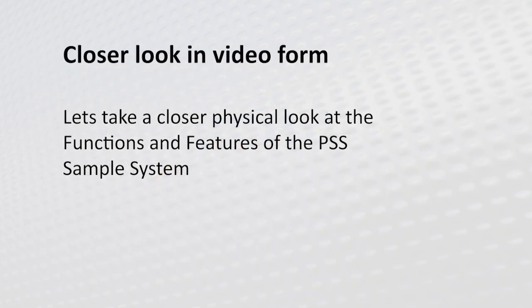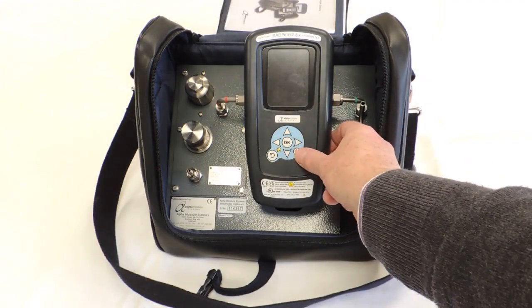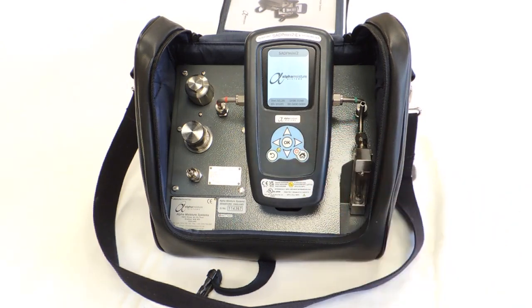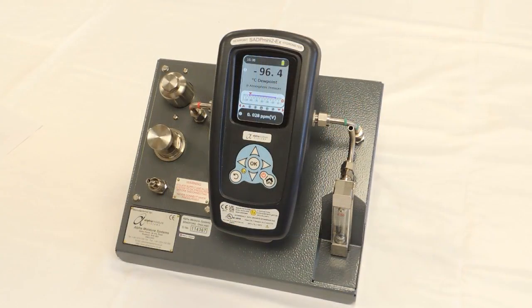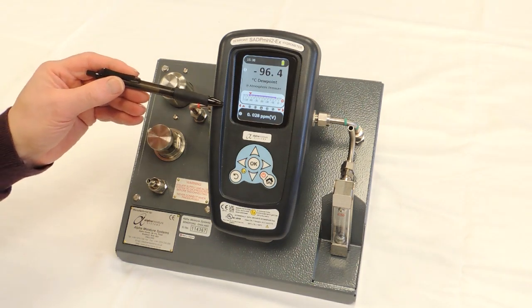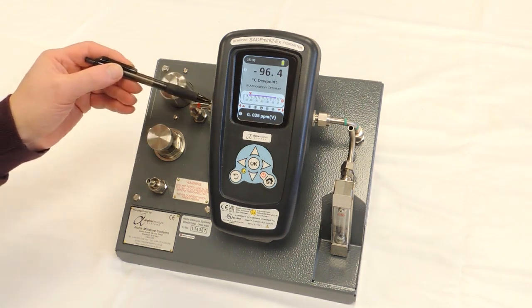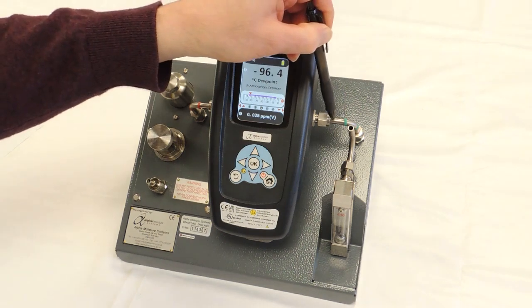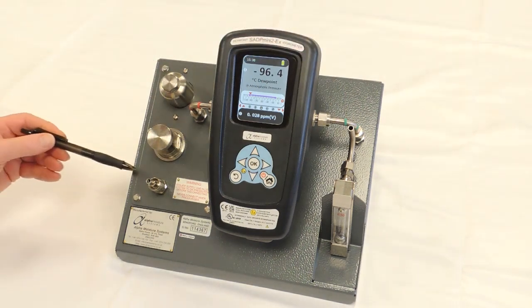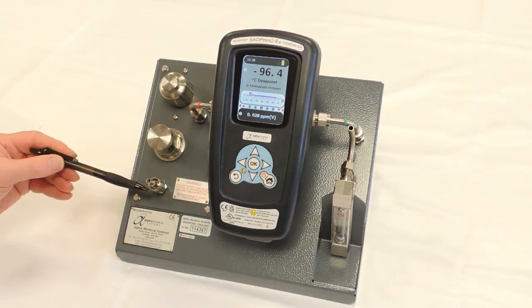Let's have a closer physical look at the functions and features of the PSS sample system. For the purpose of this demonstration, we've taken the PSS out of its carry case. Installed in the PSS is an SADP Mini 2 EX which is connected using these inlet and outlet compression fittings. The PSS is supplied on a chassis. The inlet on this example is a quick connect.